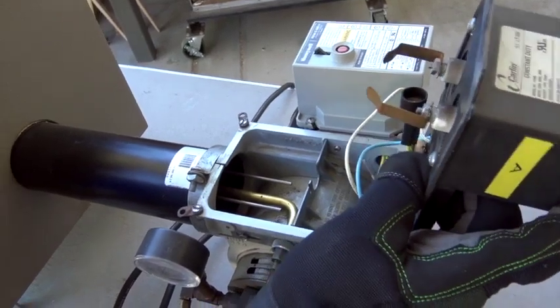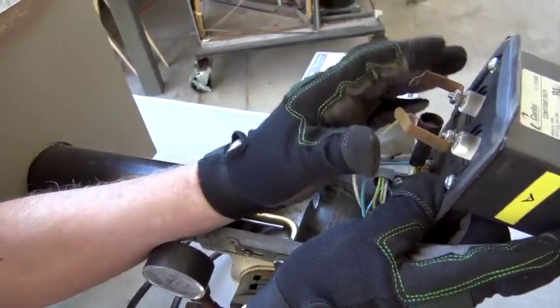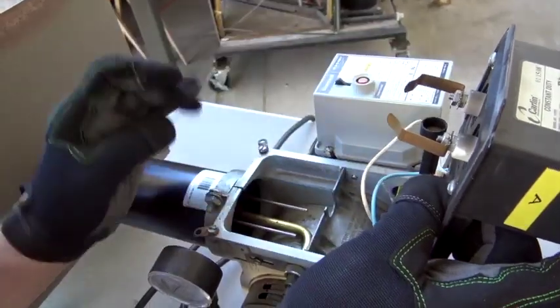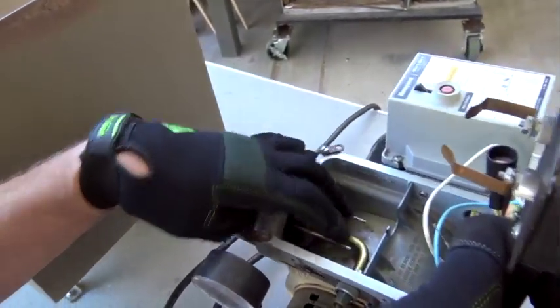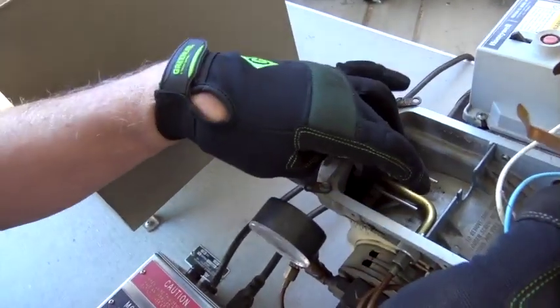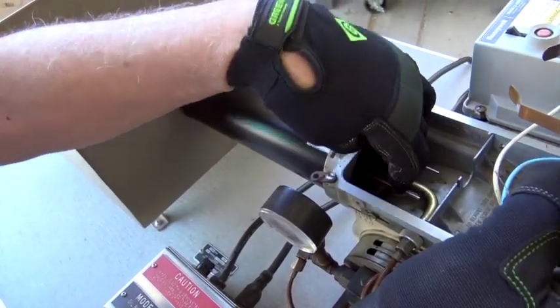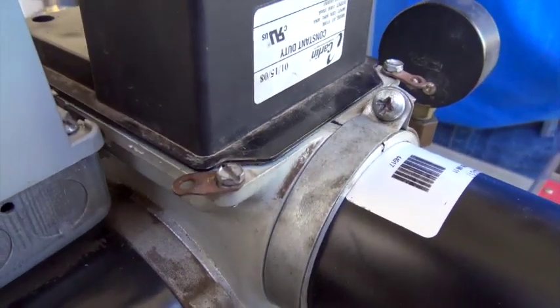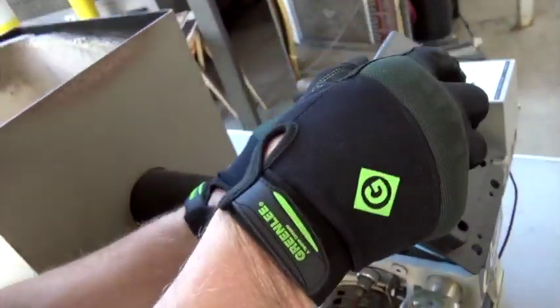So be very careful. We always see the contacts on there. These will wear out or the springs will go bad because once it sits on these two electrodes here, remember in that fire tube there? No, the fuel tube, excuse me. It has to sit perfectly on there. As you can see, someone's messed with it a little bit.